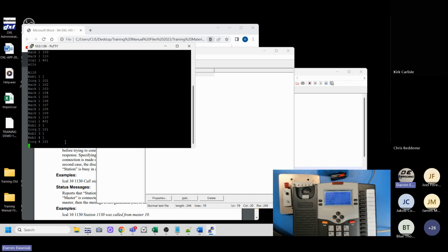So sometimes, for whatever reason, something happens and the programmers miss a message. And so sometimes I see a kludge where the programmer can't fix it. So what they will do is periodically send the stat message just in case they missed it. They'll pick it up again. So if I send stat 1 again, in case they missed it, it comes back again at this stat. So that's something you can do. I don't recommend it. I recommend finding the problem and fixing it.